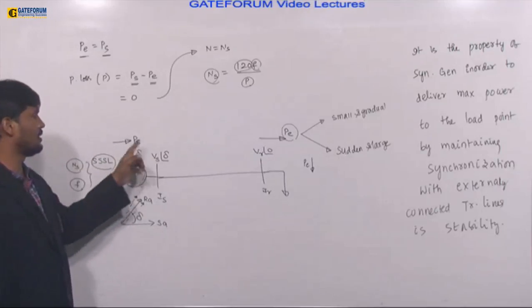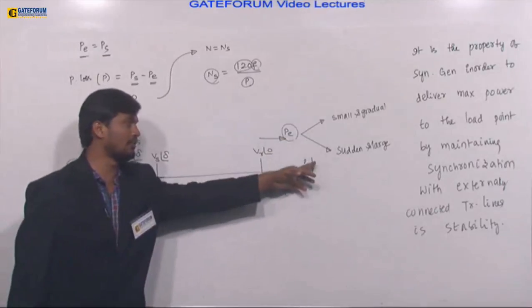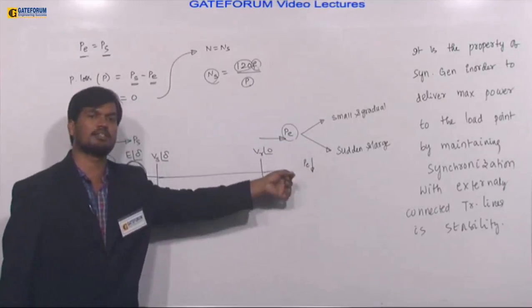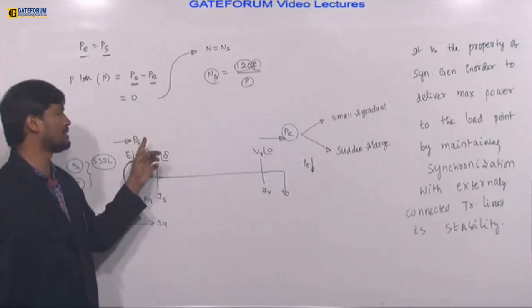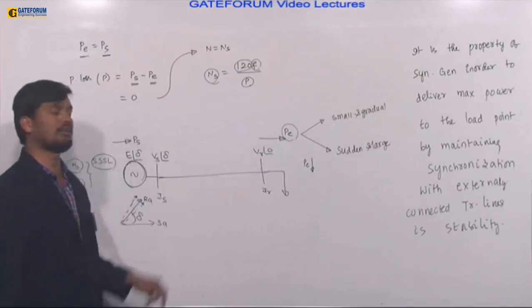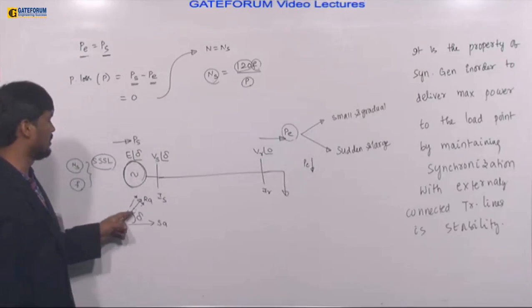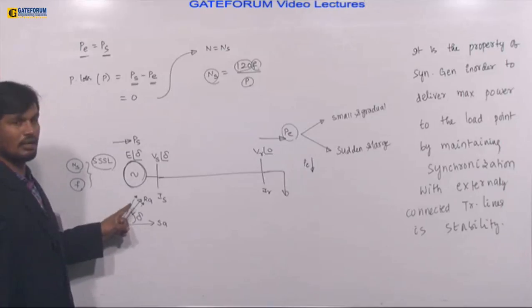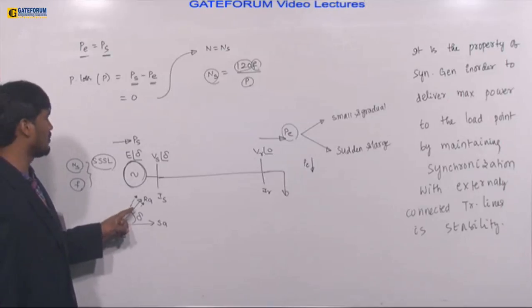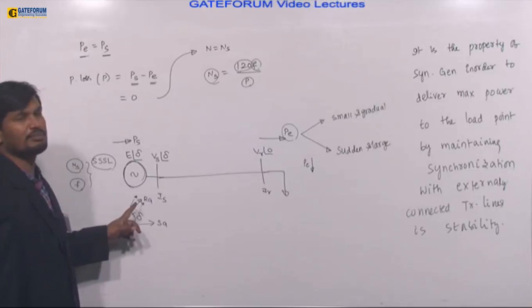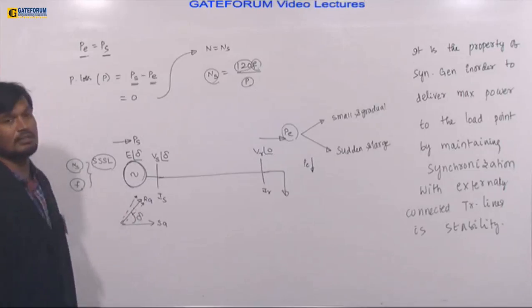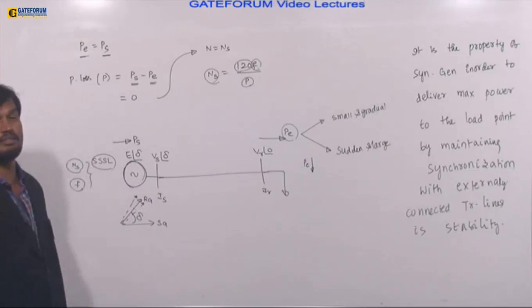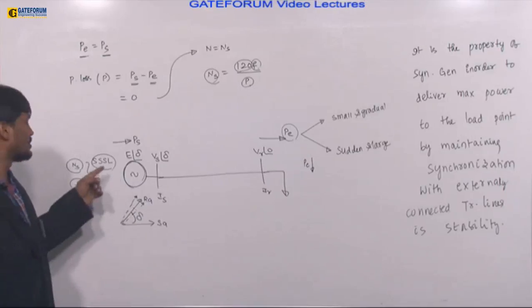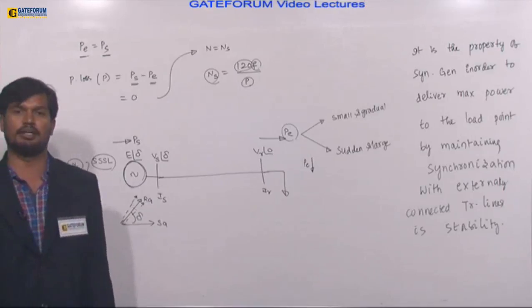With small variation, electrical output reduces or increases slightly, but mechanical input remains the same. Therefore, a difference of power arises. When this difference in power occurs, the variation of rotor angle is small. When rotor angle variation is small, variation in speed is also very small, and variation in frequency is also very small. These variations are neglected, and that stability is called steady state stability.